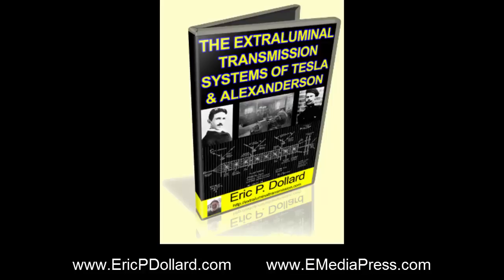No, the systems all used to be hooked in delta. So a delta connection shorts the zero sequence current out, and there's no path to ground. So the path to ground to drain the system is derived by a smaller grounding bank, which has an impedance in it, so that the fault current cannot reach significant values, if even a few amperes. And if there is a fault current in that line, then that goes to ground off the balancing or the draining transformers, the grounding transformers, then that relays the system out. But the way the system's configured now, it can't relay that out because the transformers are Y connected and they're solidly grounded, and the system has a neutral or a fourth wire. So any current flowing from line to this multi-grounded neutral is the same as a current flowing from that line to a wire laying on your car or it hit you or something, and it cannot distinguish the current.